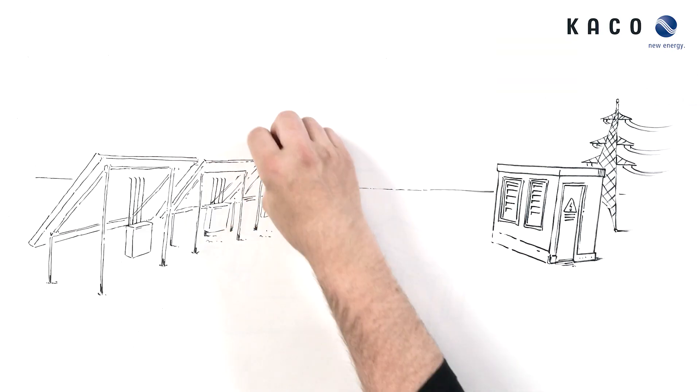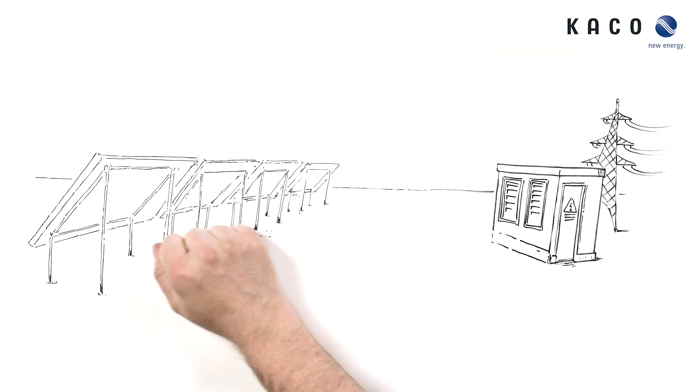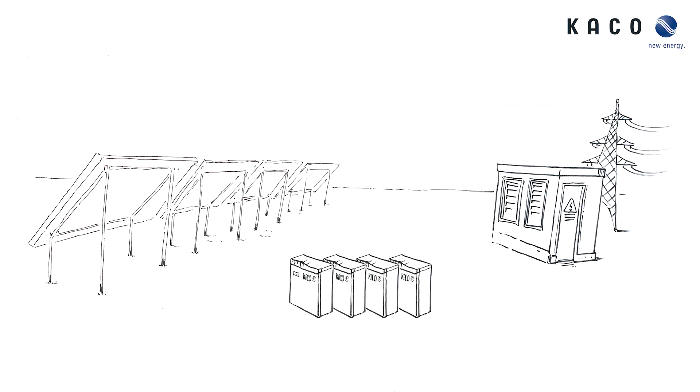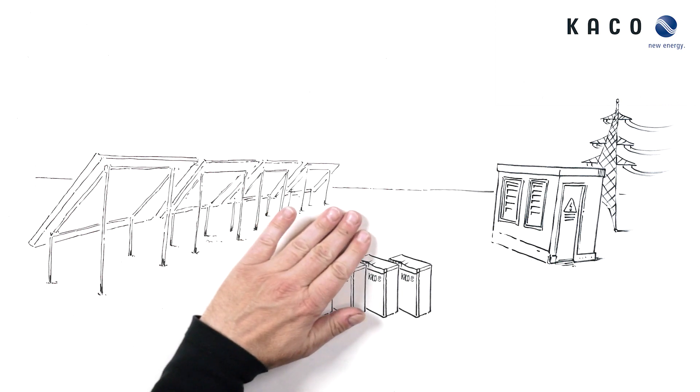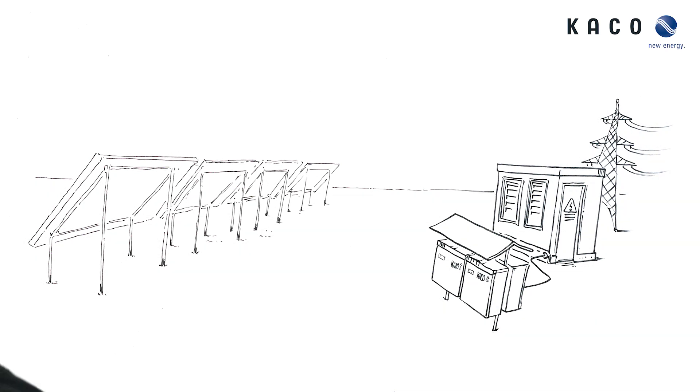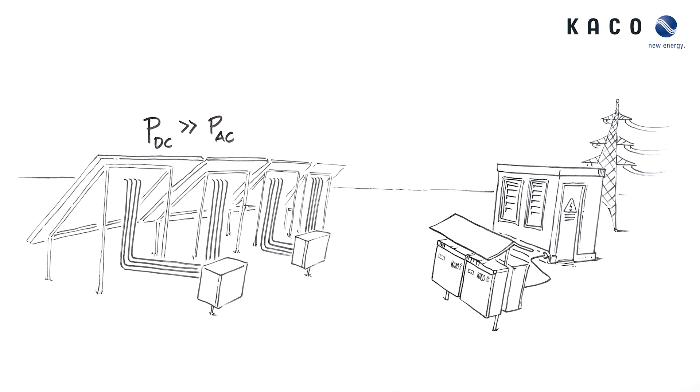And now, we swap ordinary inverters for KACO new energy's Blue Planets with a single MPP tracker. Move them onto a central rack near the transformer and collect the DC strings in a combiner box near the PV generator. Finally, we connect each box via one DC main cable to the input of a Blue Planet.